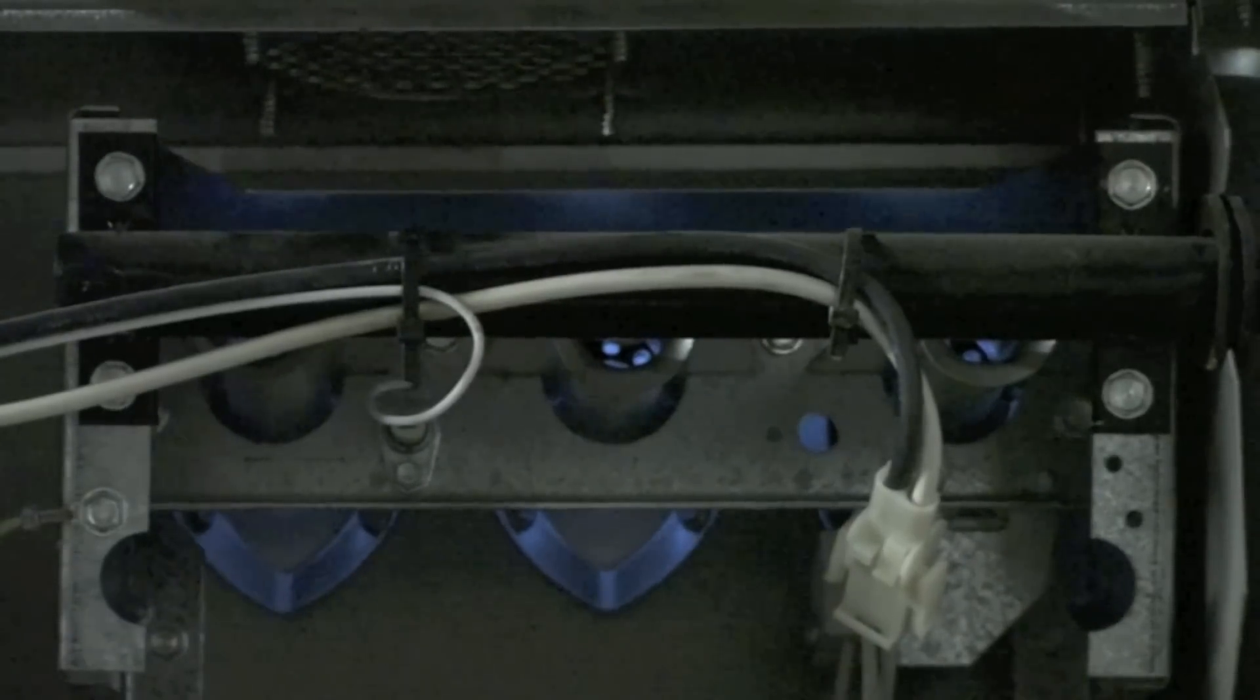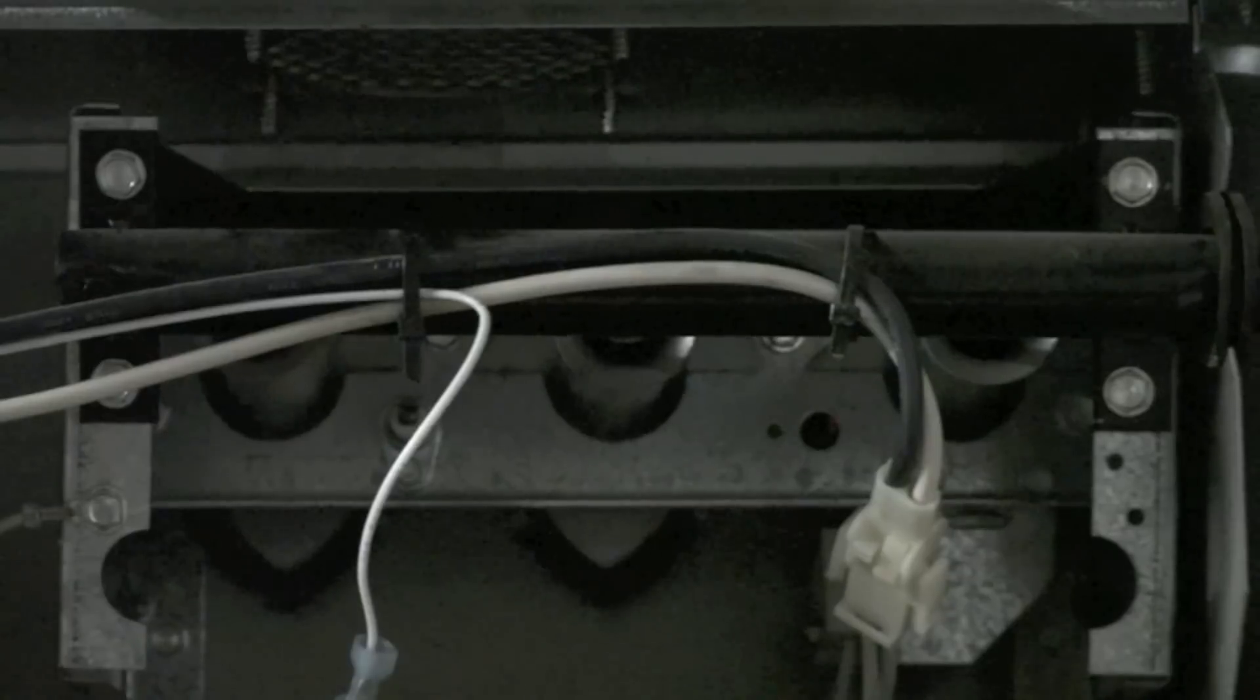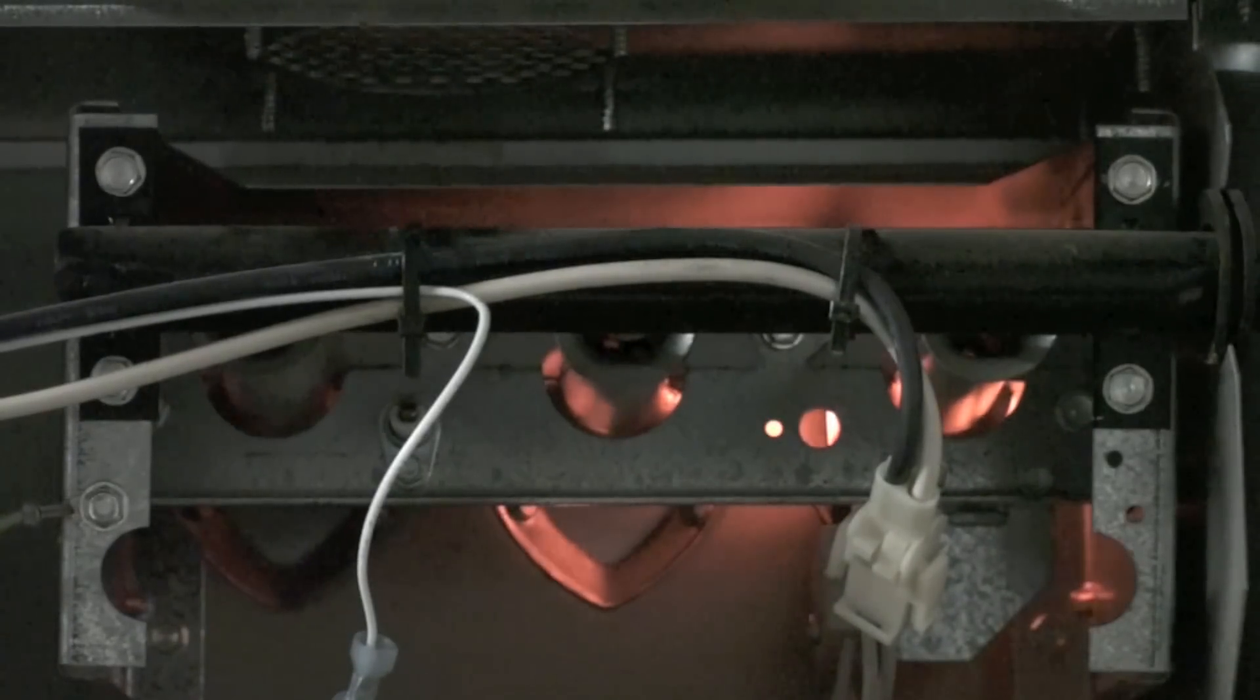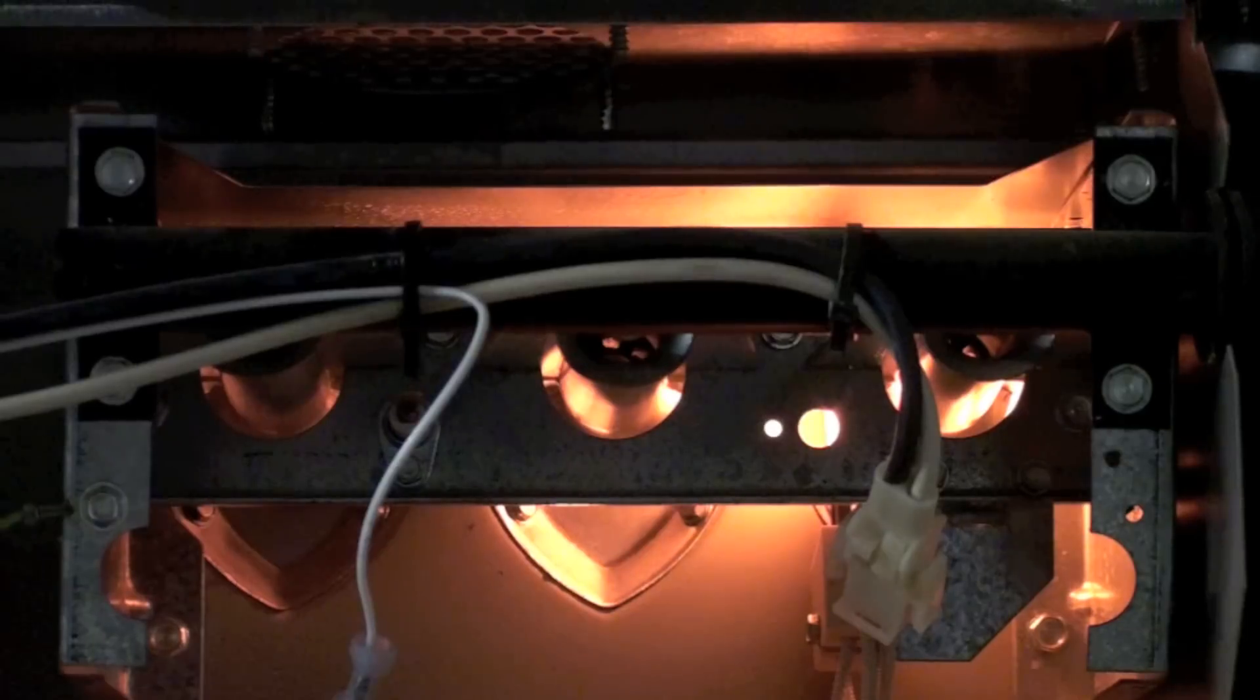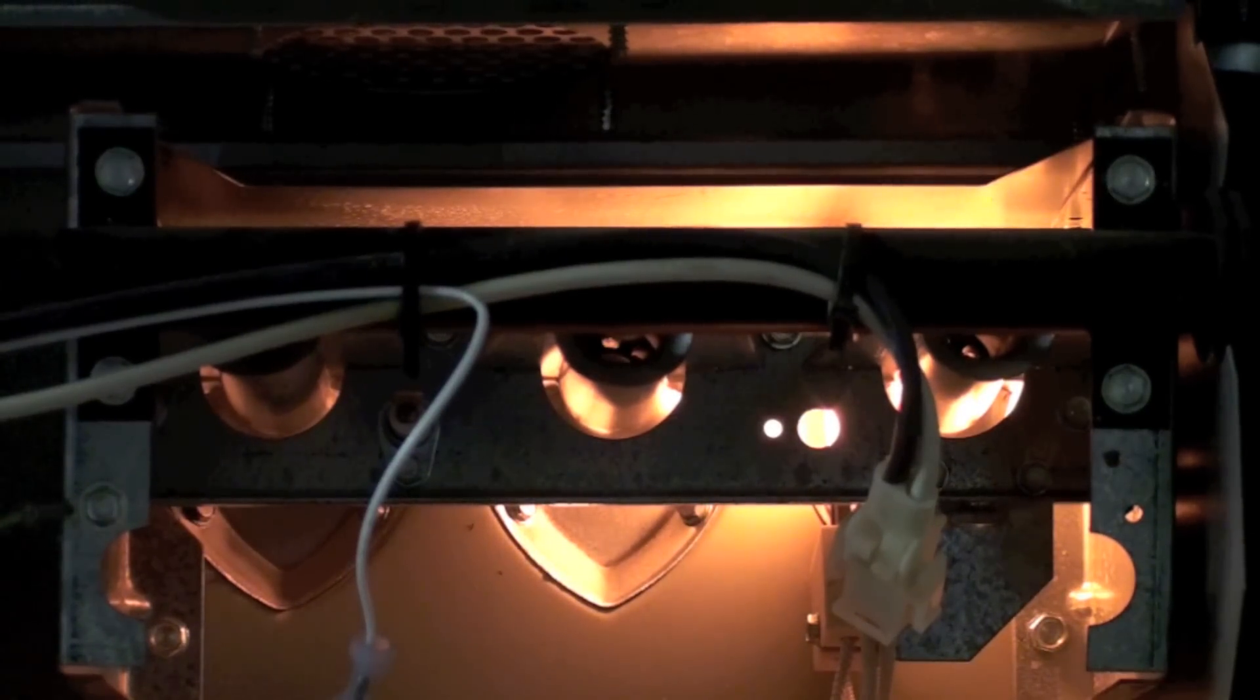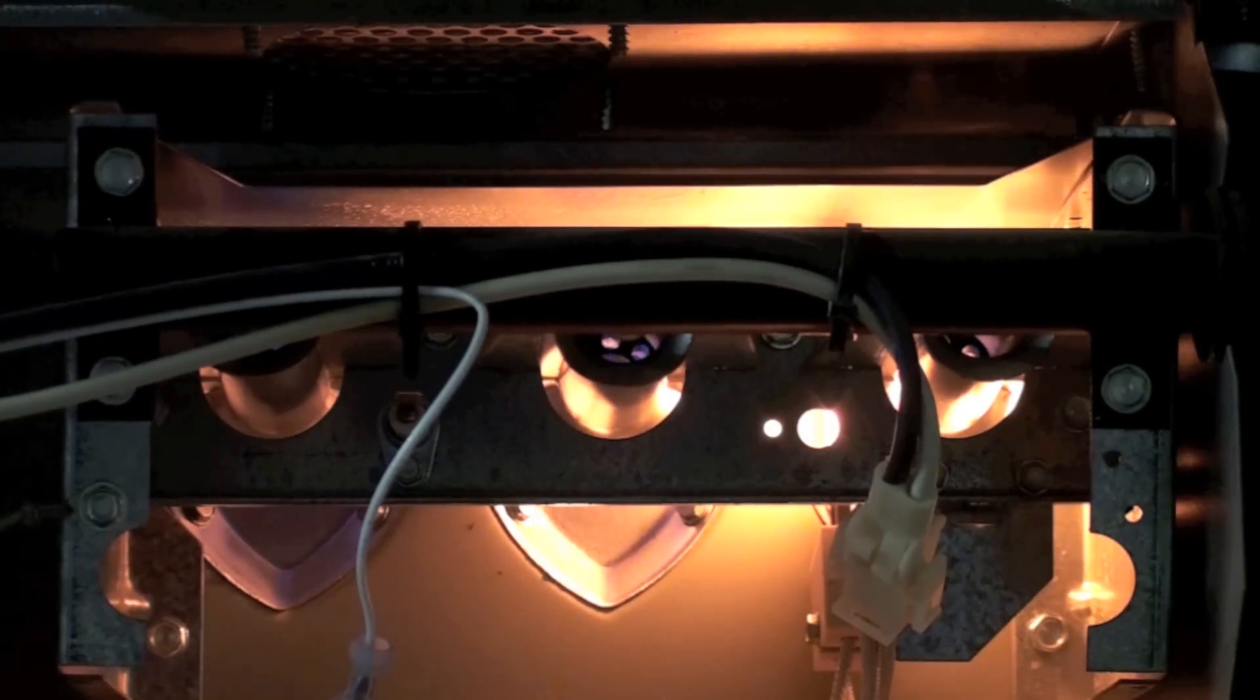You can see that blue flame in there. Where we get abnormal is if for some reason we lose that flame signal, it's going to shut off and it's going to try again. You can see that hot surface igniter come on. Okay, there's your flame.